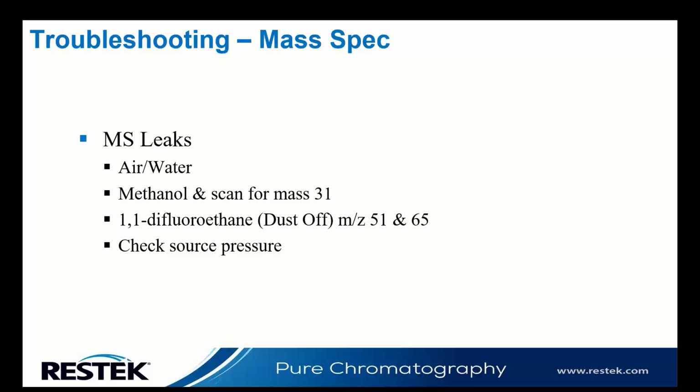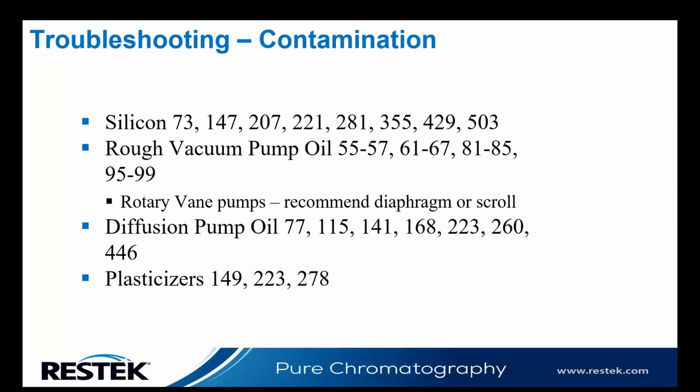And so it's much better to use a leak detector because that's going to be under pressure. That part of your system is under pressure and you're able to do a troubleshooting that way and see that leak. So troubleshooting contamination, we're looking at silicone.